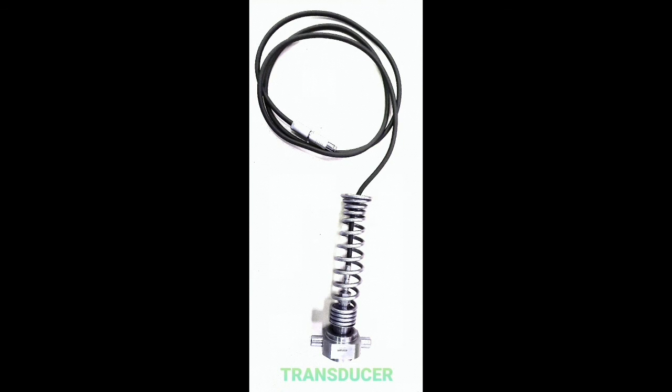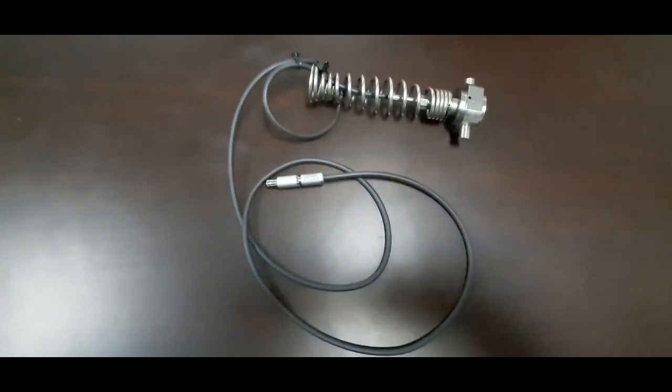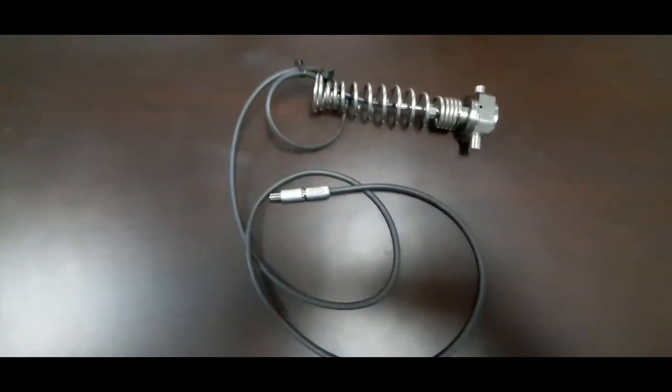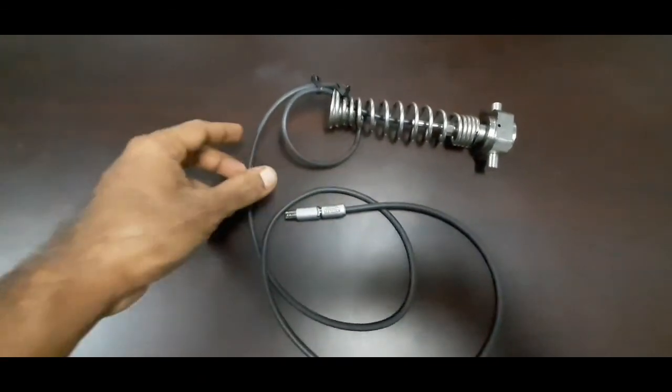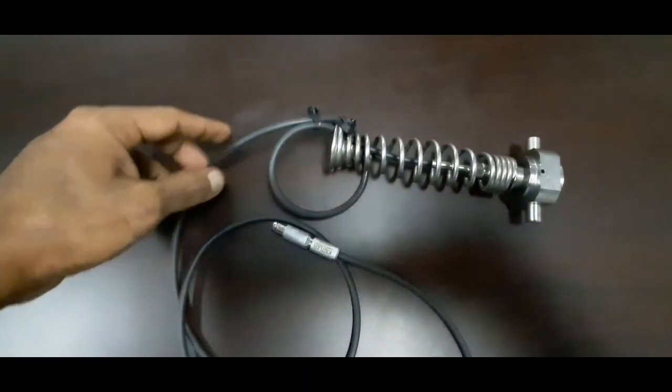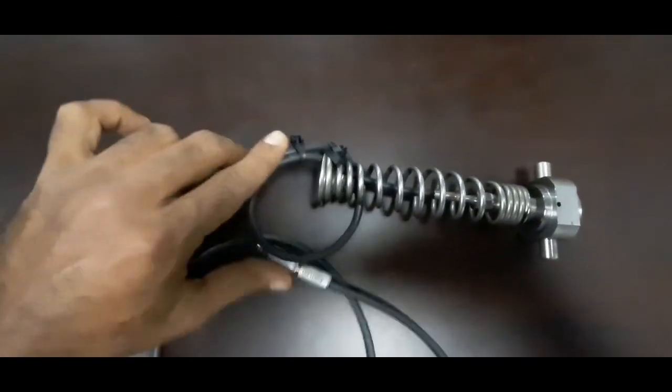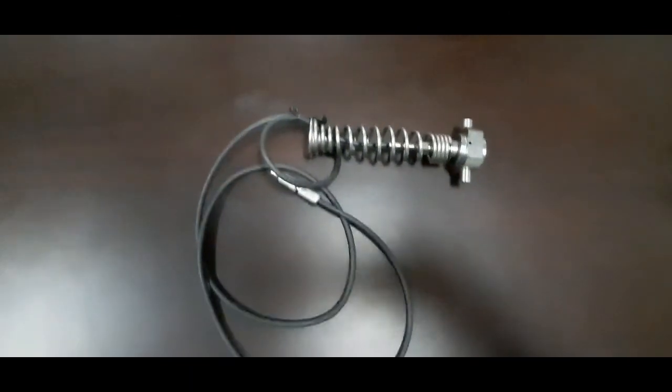Friends, this is very important. During the process of this measurement you need to take due precaution while handling the cable of the transducer. The connections are delicate and the transducer can malfunction if you handle it roughly. Never hold the cable with the weight of the transducer on it. It is always advisable to secure the cable at the top with an electric cable tie.